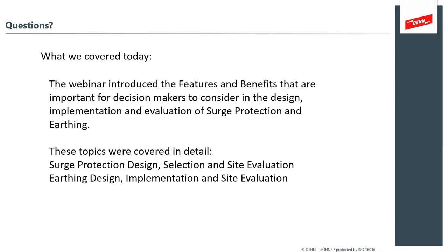A follow-up question is relative to the same aspect. The person asks, in the risk assessment, how does the lightning protection level selection affect the surge protection specification? Well, this is really a great portion of the IEC methods, because IEC pays a lot of attention to the direct strike energy that's associated with lightning. The NFPA and UL methods, although they're very thorough, don't have some of the same testing of direct strike lightning energy on SPD devices.